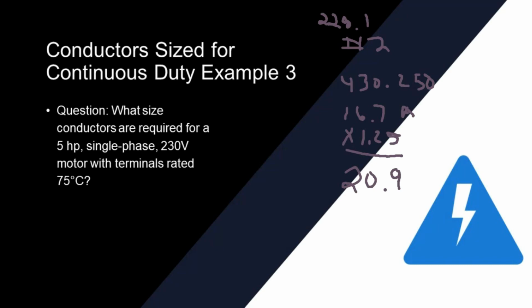Column A and column B is of note on this table. If you look at column A, there's a little note that says A1 and B2. Okay? So under the bottom of the table notes, it says the currents under column A apply to 3 conductor cords or multi-conductor cords connected to utilization equipment so that the 3 conductors are current carrying. The conductors under column B are 2 conductor cords and other multi-conductor cords connected to utilization equipment so that only 2 conductors are current carrying. So that's the difference between column A and column B. So at 20.9, the answer here is 11 gauge, or D. For 228.1 number 2, the answer is D.